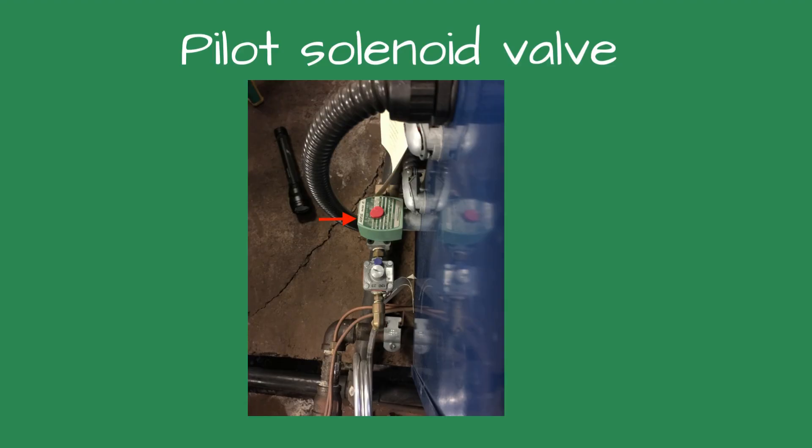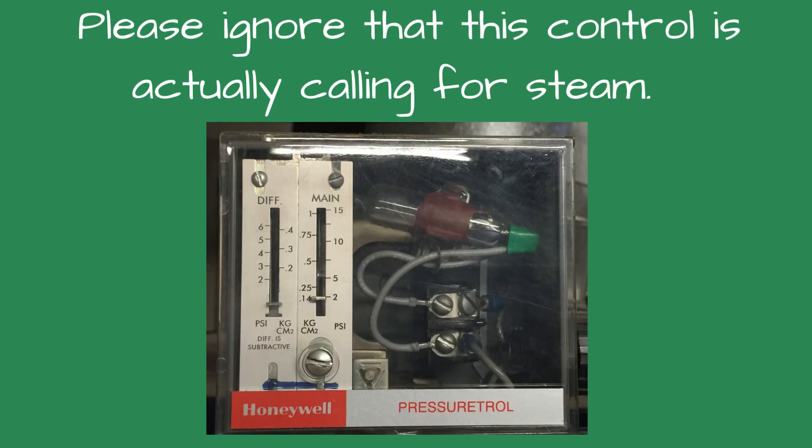When I arrived, I determined the pilot's solenoid valve was defective on the lead boiler. Tracing the control wiring for the lag boiler, the operating steam pressure control was keeping the boiler off.